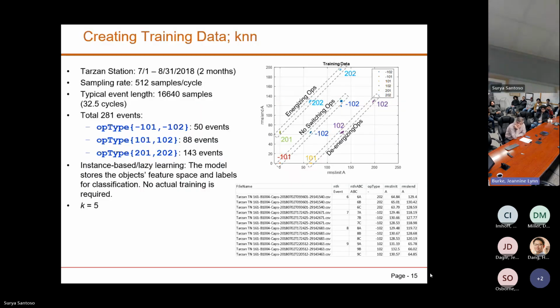So in here, de-energizing and energizing, the slope is the same because the capacitor size is discrete, one bank at a time. They don't energize two banks at the same time because this is a three-phase capacitor bank, and each phase has its own circuit switcher, and they are gang operated, meaning if one phase energizes, all phases energize like that. But there is always a time difference, maybe a few cycles, but never exactly the same. But at the end, this is what you see.